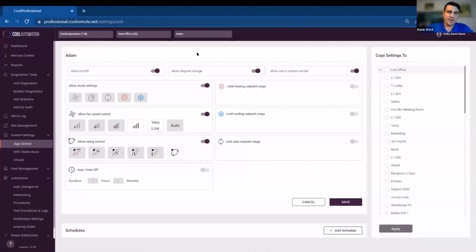Thanks again, Ben. So this is going to fall under the control settings section of our professional app. From here, we allow for any type of restrictions, whether that is from the remote control app itself or locally at your wired controller. From the app, we can very easily set a heating set point range or a cooling set point range, also in auto. You can completely disable the user's ability to turn a unit on and off or allow a set point change. Or if you want it to be completely removed from the remote control section of our app, you can do that as well. These settings create a template that you can then apply to any of your indoor units or your entire site.